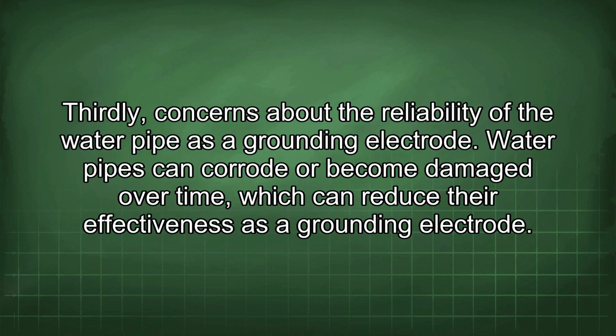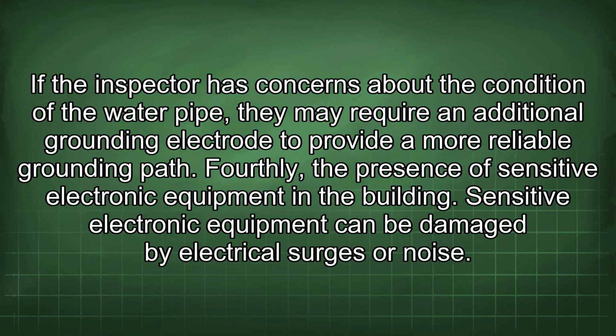Thirdly, concerns about the reliability of the water pipe as a grounding electrode. Water pipes can corrode or become damaged over time, which can reduce their effectiveness as a grounding electrode. If the inspector has concerns about the condition of the water pipe, they may require an additional grounding electrode to provide a more reliable grounding path.